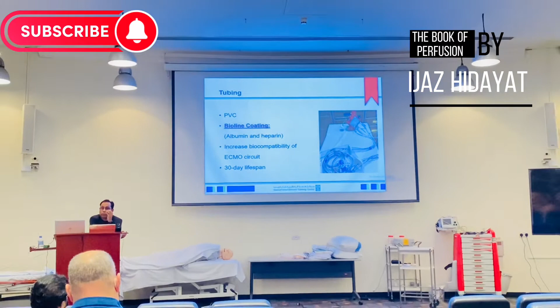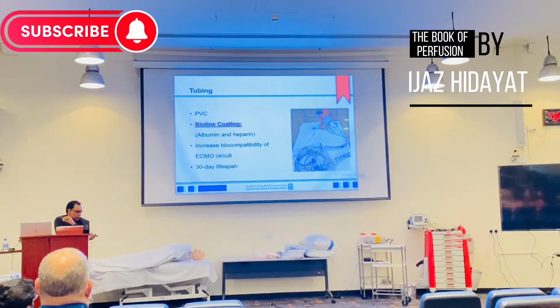This is by the manufacturer, but it can go more than 30 days. It doesn't mean that after 30 days you are going to remove it, and it can also be less. It depends on the patient's physiology and hematology. You may need to change the circuit within 1 day or 2 days, or it can go for like 2 months, so you don't need to change the circuit. Actually the lifespan of the circuit and oxygenator is like 30 days.